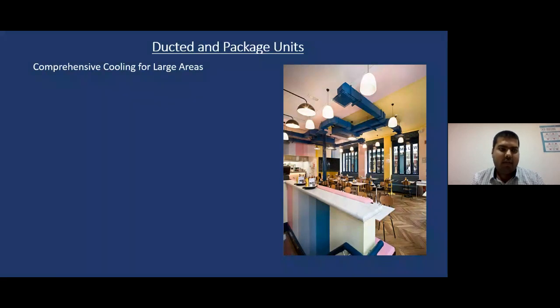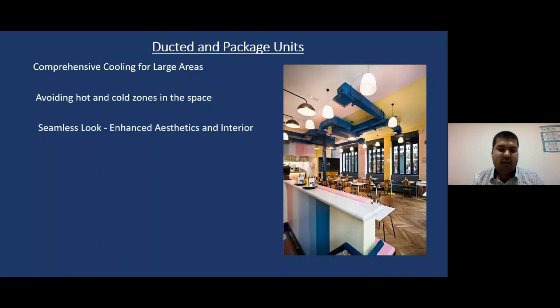With a ducted and package unit, it gives comprehensive cooling for larger areas, for applications like banquets. With the equal division of airflow in every area of the room, it avoids hot and cold zones in the space. Like if I install a split AC in a larger space, a person sitting in one corner would feel too cold and another person would feel too hot. But with a ducted AC, this problem is completely avoided. Then it gives the seamless look. Most architects are huge fans of ducted units. With rectangular ducts, spiral ducts and round ducts, there are a lot more options to play with for the false ceiling and the interiors. So it gives better aesthetics and a very nice interior to the rooms.